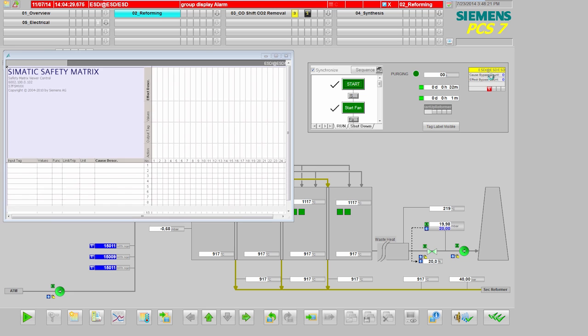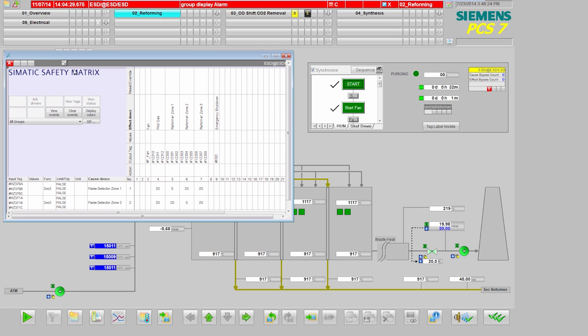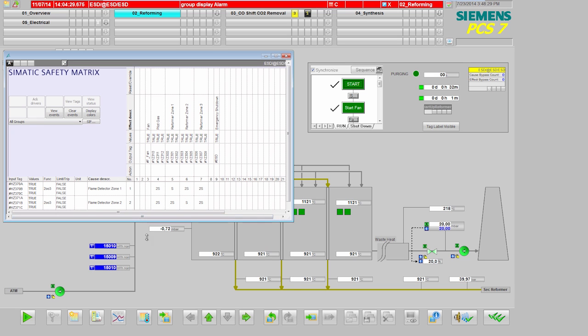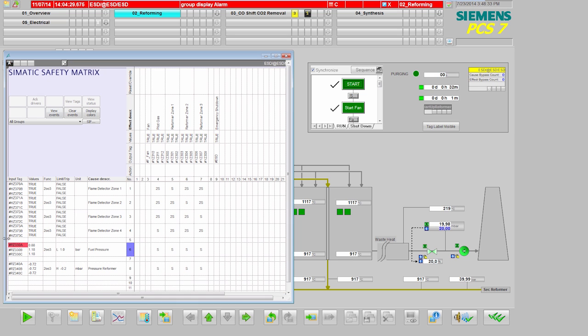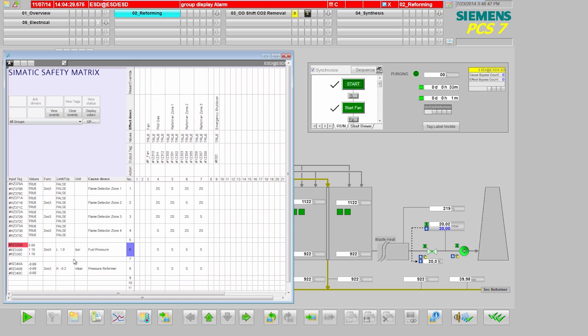I am now opening the safety matrix and checking the safety application to see what this means. Here I can see that the value at one of the measuring points is lower than the permitted limit of one bar. Because the values at the other two measuring points are still within the permitted range, it means that two of three is okay, so the fuel infeed remains open.